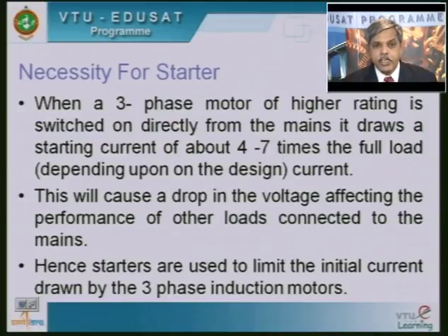So, this higher amount of current drawn by the motor at the time of starting causes a large voltage drop in the supply lines which are connected to other loads. At the time of starting, the larger voltage drop taking place in the lines will affect the performance of the other equipment connected to the same supply. So, to limit the starting current to a safe value, we need a starter for the induction motor.